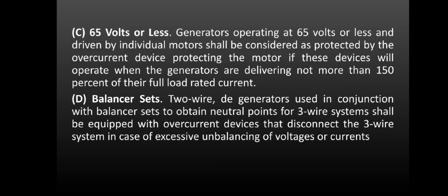C. 65 volts or less. Generators operating at 65 volts or less and driven by individual motors shall be considered as protected by the overcurrent device protecting the motor if these devices will operate when the generators are delivering not more than 150% of their full load rated current. Balancer set. Two-wire generators used in conjunction with balancer sets to obtain neutral points for three-wire systems shall be equipped with overcurrent devices that disconnect the three-wire system in case of excessive imbalancing of voltage or current.